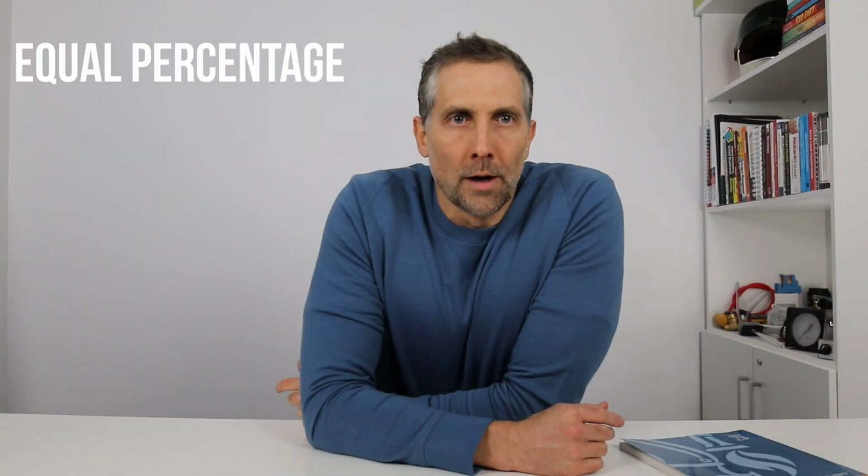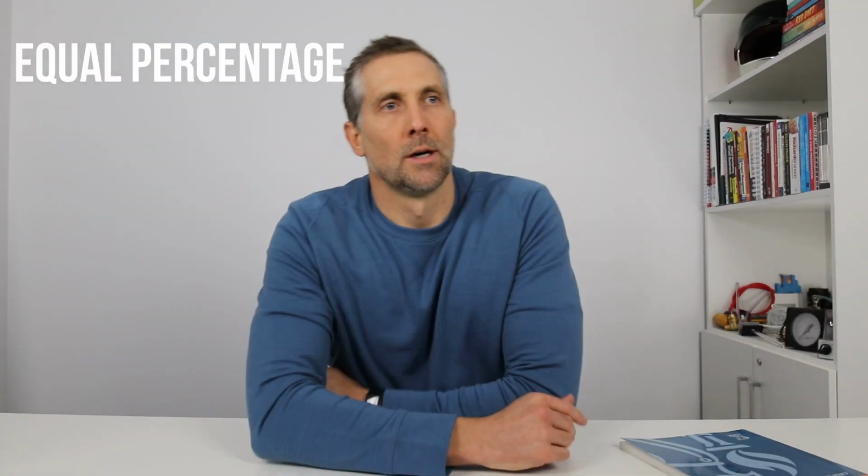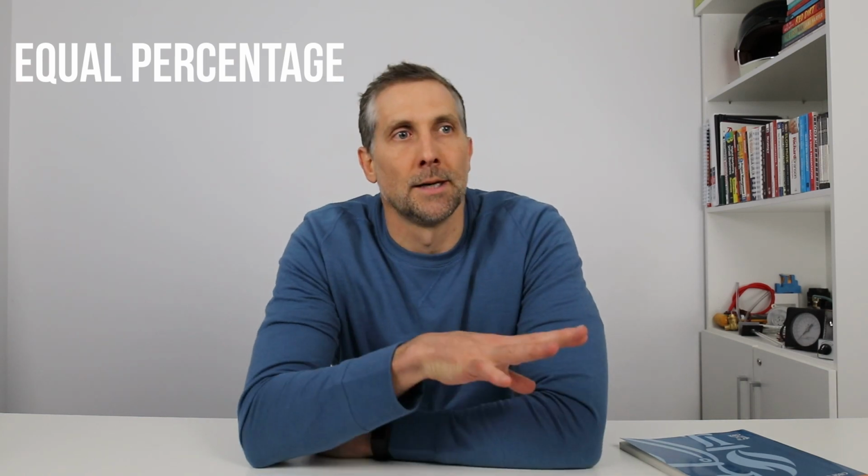I wanted to follow on from last week's discussion on valve authority, where we discussed the difference between sizing 2-port control valves and sizing 3-port control valves. Because I think by now we would all probably agree that we're not sizing 2-port valves properly, and we're probably resulting in lower valve authorities below 0.5, especially as we move closer towards where the pump is.